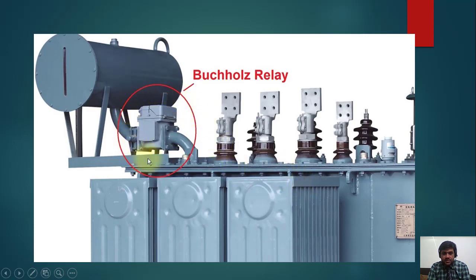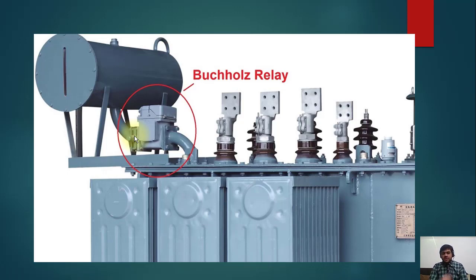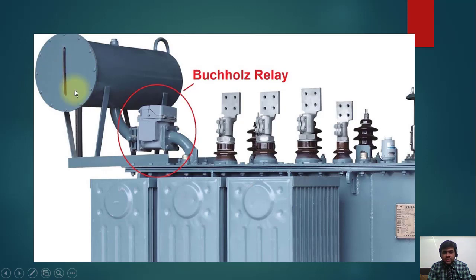This is the actual real picture of the transformer — here you can see what the Buchholz relay looks like. This is the conservator and this is the main body of the transformer. You may ask: why do we need a conservator? The answer is that oil expands and contracts as heat increases or decreases, so the conservator provides a buffer margin to allow the oil to expand or contract.